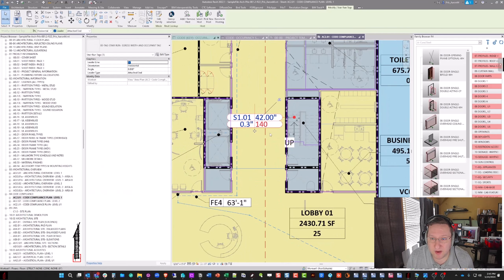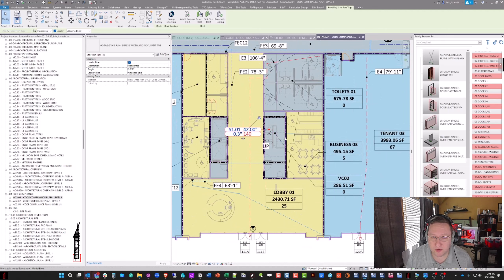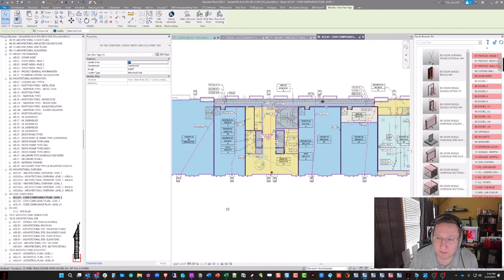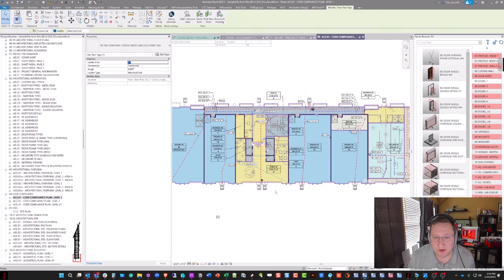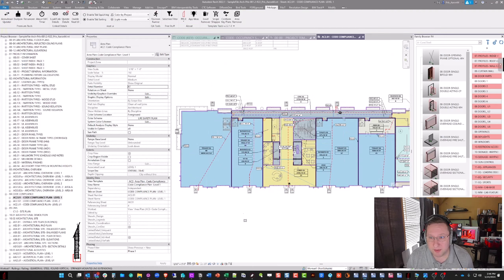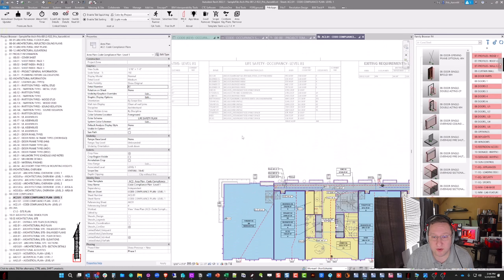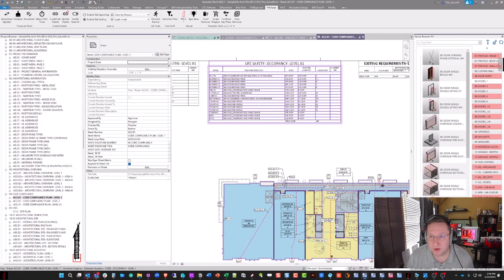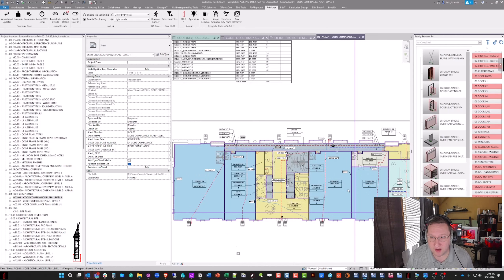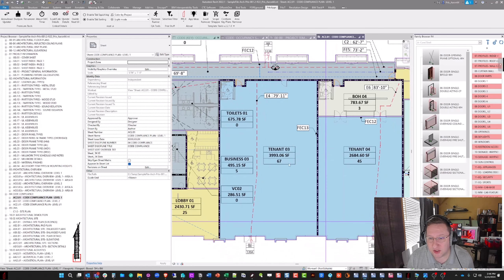All of the distances we want to tag with a length are done using modeled railings. Several years ago Revit did create a specific path of travel tool, but it still has some shortcomings graphically compared to using the railing methodology. There are certain railing types shown here — it's at every firm's discretion, not all are required to be used. We have travel distances and egress paths that we prefix with a capital E when we tag them with their length, and that generates the egress path schedule. We use the same tag on a different railing type called common path of travel, prefixed with a C — those do not go into the travel distance schedule.